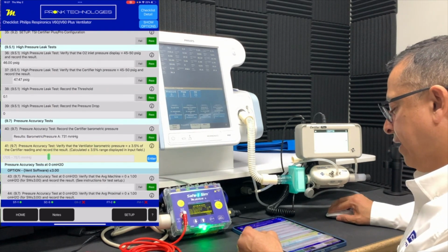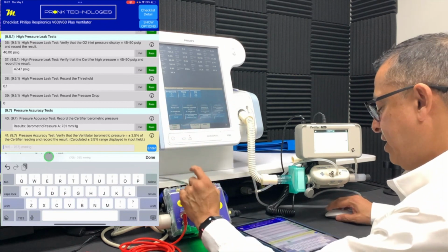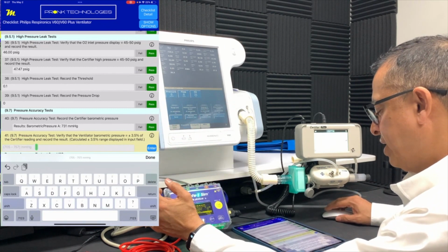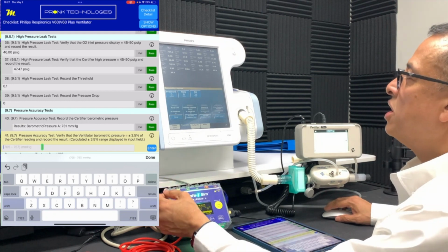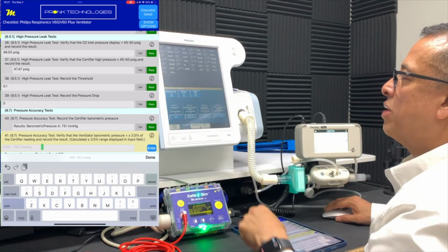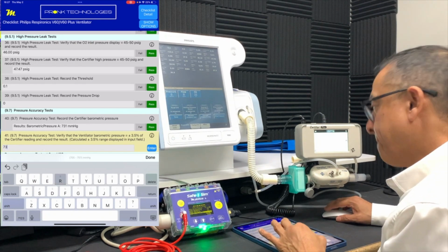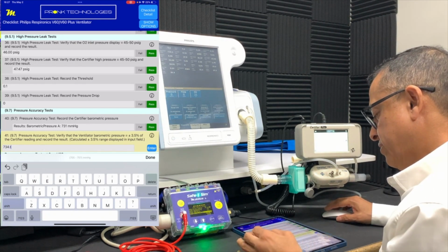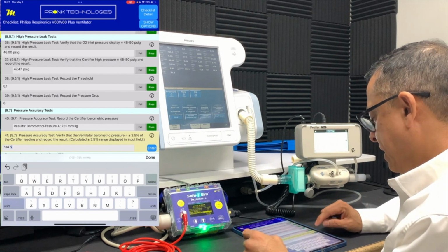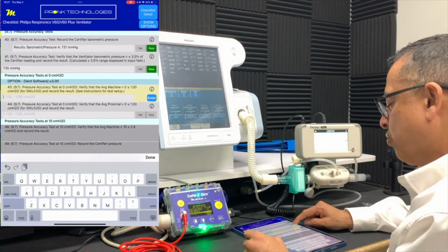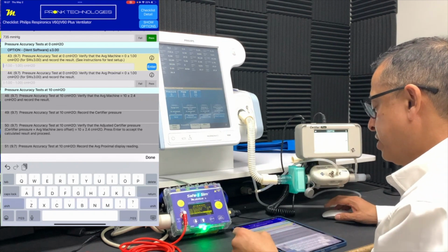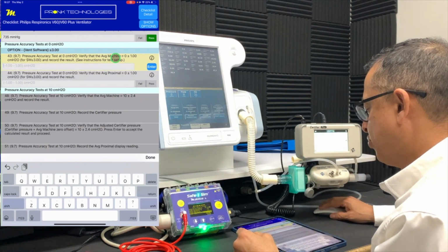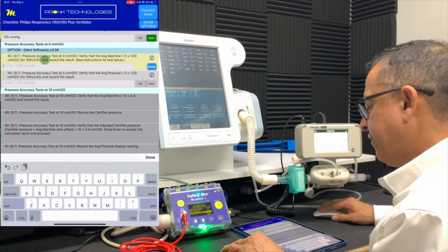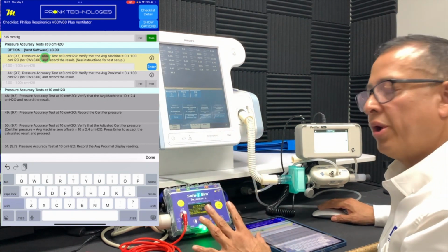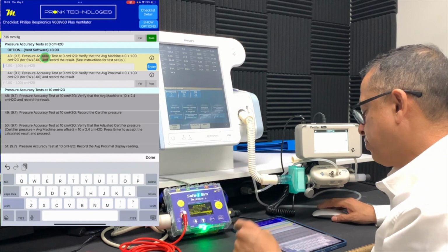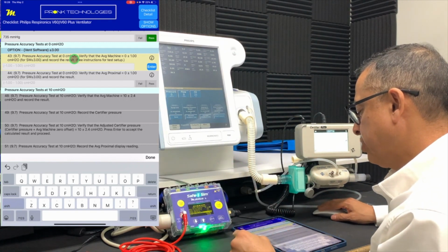And now we need to record the barometric pressure on the ventilator itself. You can see here in gray, it gives you the pass-fail ranges already within the procedure, so there's no guesswork going on here. So our barometric pressure on the vent is 734.5. So we've captured that as our reference. Now we need to make sure we check our pressure at 0 centimeters of water. We need to check the average machine pressures within that range, and this is given the software revision of the ventilator, which is at 3.0. So we made sure that this test does correspond to the procedure as we need to.